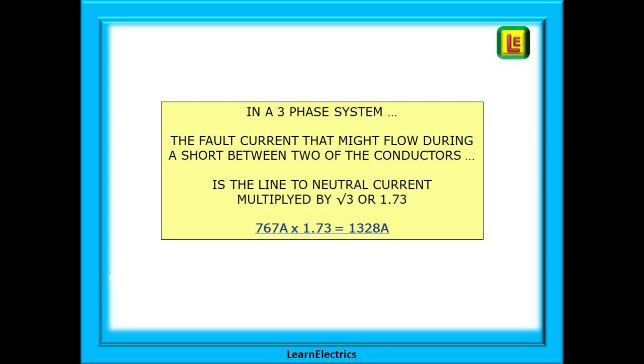So what have we found out? In a three phase system, the fault current that might flow during a short circuit between two of the conductors is the line to neutral current multiplied by the square root of 3, or 1.73. In our example, 767 amps multiplied by 1.73 is 1328 amps.